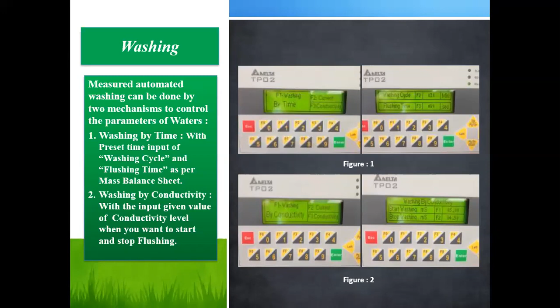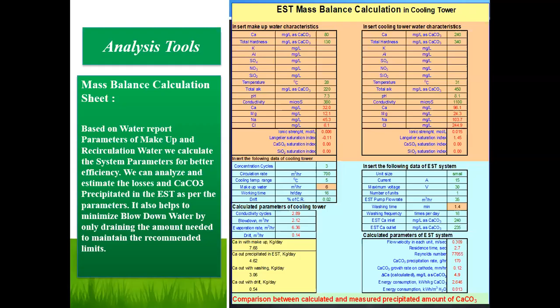There are various analysis tools. You can see a mass balance analysis tool shown here, where you can input all the parameters like calcium, the ongoing water parameters, calcium hardness, alkalinity, and pH. Based on that, you can calculate the amount of blowdown required, and what should be the washing time and washing frequency of the system. It also gives a technical calculated idea of how much calcium is coming in, how much will precipitate in the EST, and how much will be washed out in a cycle per day.